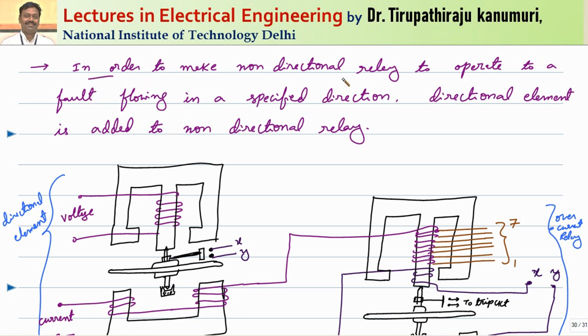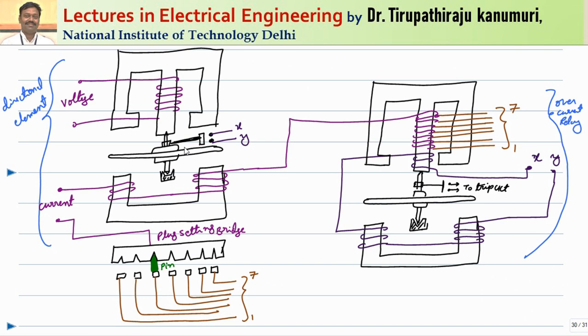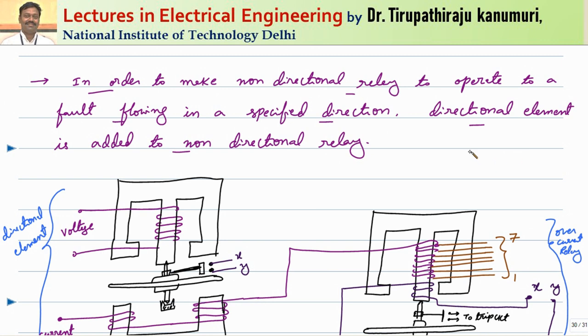In order to make this non-directional relay operate for a fault flowing in a specific direction, one extra directional element is required, added to the non-directional relay. To find the direction of power, we take a reference voltage. Under normal fault conditions the current is lagging. If the direction of power is changed, the voltage is not changed but the direction of the current is now reversed.